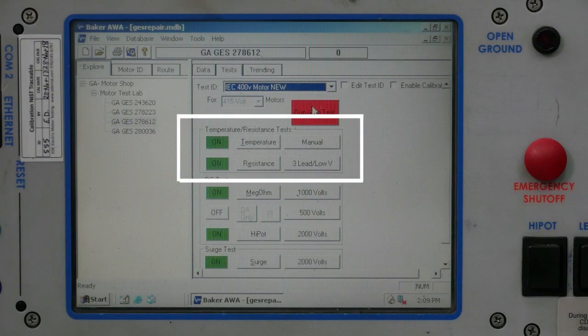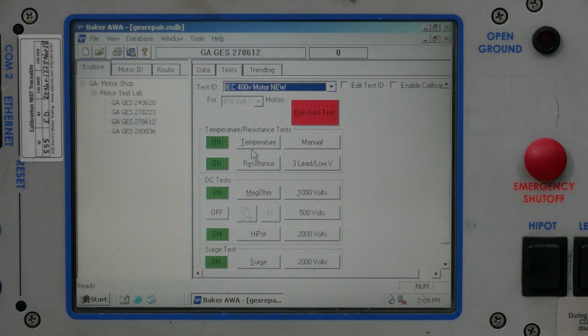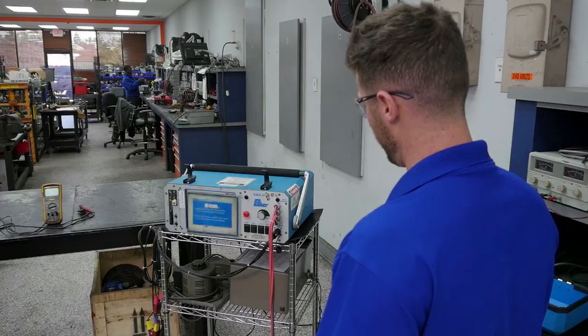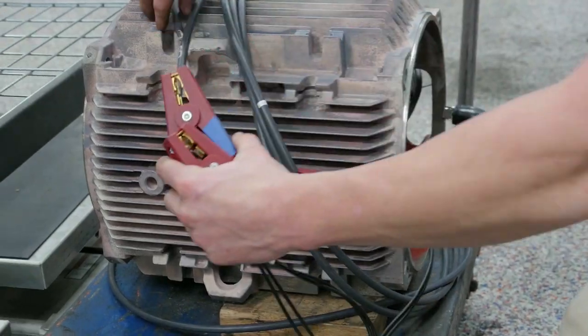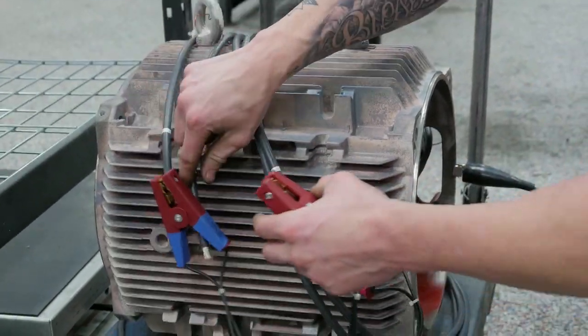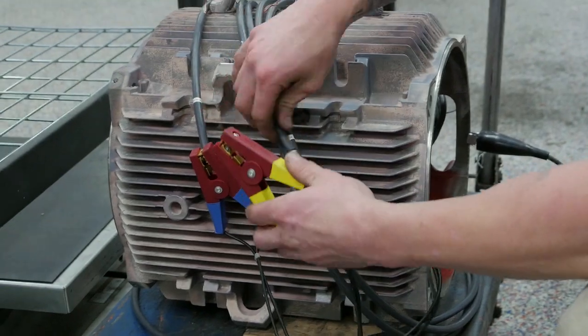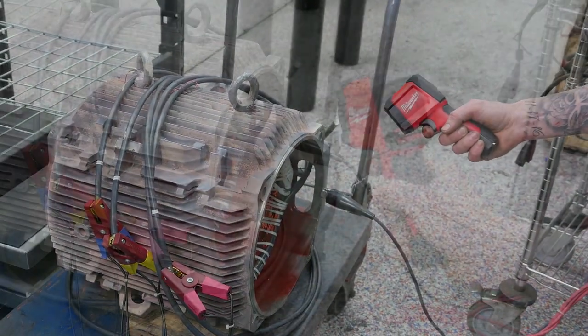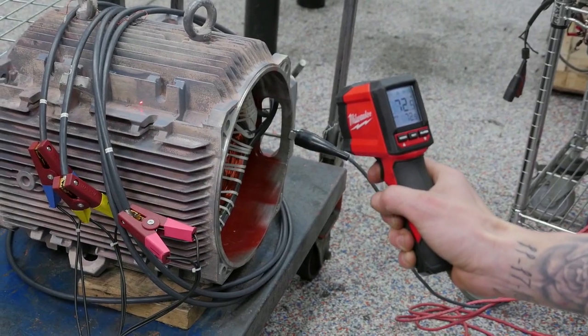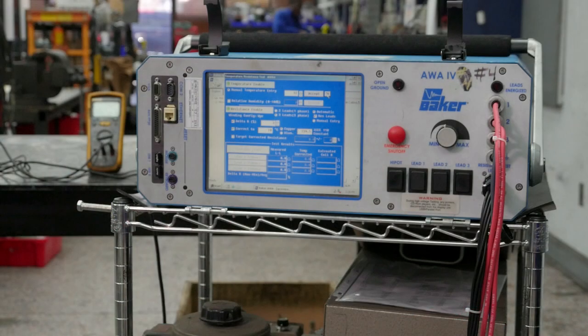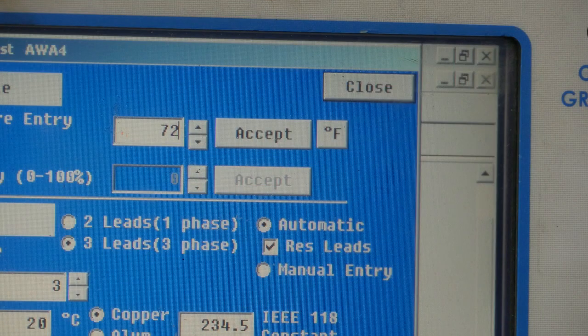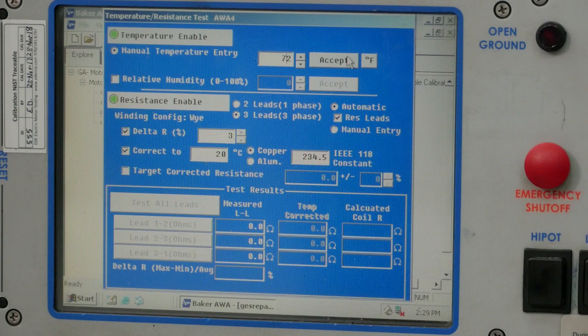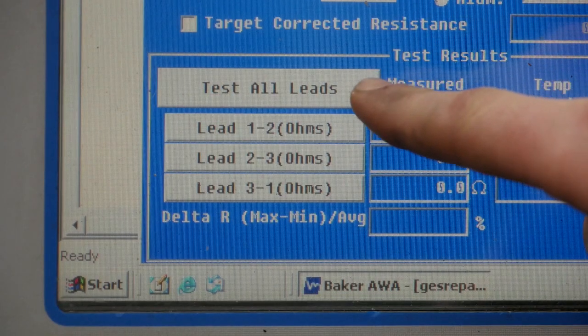This test is looking for an imbalance of resistance between the motor phases. Since temperature can affect the resistance properties of a motor, this test is performed at a known temperature. First, the technician hooks up his low-voltage leads to the motor's power connections. Then he will take measurements of the average temperature of the motor. Here, he will input the temperature, then select to test all leads.